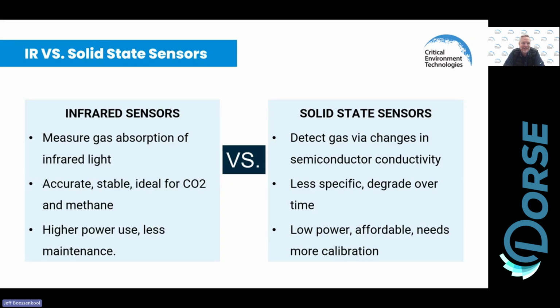The only downside, I guess, that you could say when it comes to infrared sensors is that they're more expensive, right? But again, if you think of what the purpose of this gas detection system is, yes, it's for the protection of life and property, but it also has to have the confidence of the building managers, right? If we put a solid state sensor in there and we start getting false alarms or incorrect readings as a result of cross-contamination or poisoning, that is going to lead to a lack of confidence in the system, and that's not where we want to be when it comes to gas detection. So again, for refrigerants, strong recommendation towards the infrared sensor.